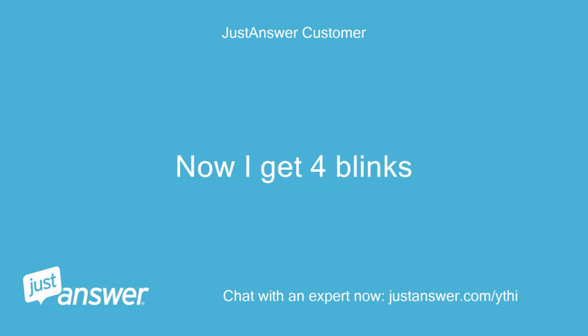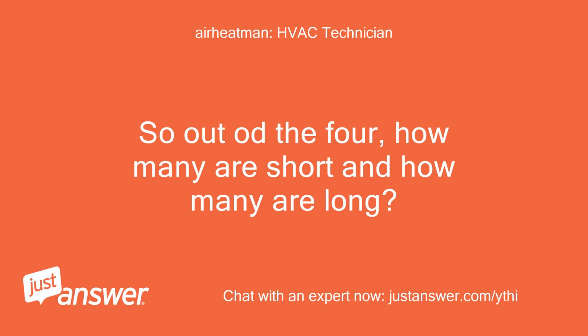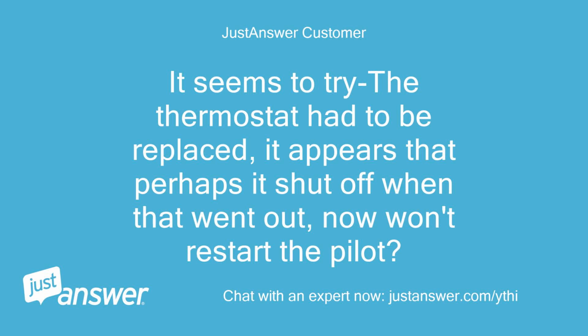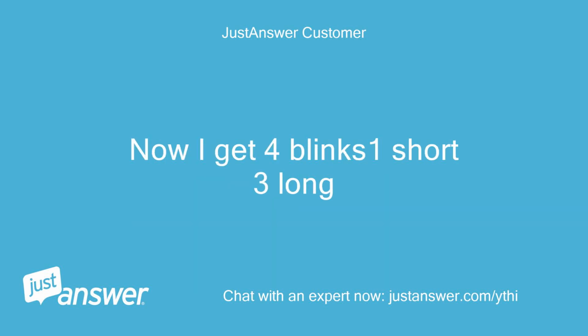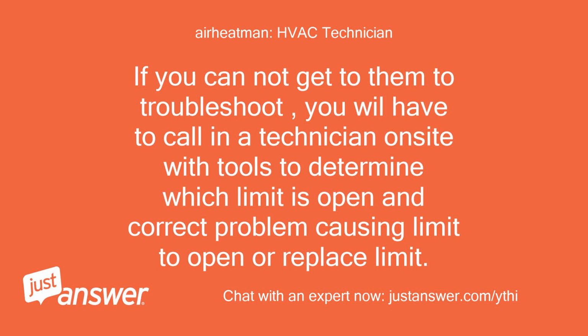Now I get 4 blinks. The errors are going to be in short and long blinks. So out of the 4, how many are short and how many are long? Now I get 4 blinks, 1 short, 3 long. That is still indicating one of the limits is open. If you cannot get to them to troubleshoot, you will have to call in a technician on site with tools to determine which limit is open and correct problem causing limit to open or replace limit.